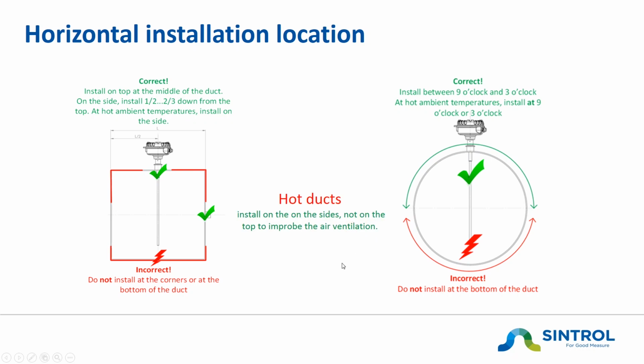For hot ducts, we recommend an installation on the side so that the natural air vent will cool down our instrument. For installations with very low flow speeds, I would recommend an installation a little bit on the lower side of the duct, as here are all the big and heavy particles.